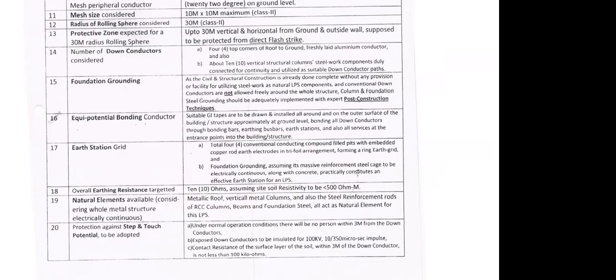Protection against step and touch potential is to be adopted. We discussed this, but again, exposed down conductors are to be insulated for 100 kV 10/350 microsecond impulse. That means even though it is not recommended, if due to some compulsion we need to do it, then we need to protect it either through a camouflage or through a sleeve provided.